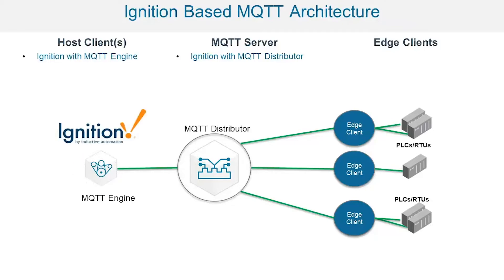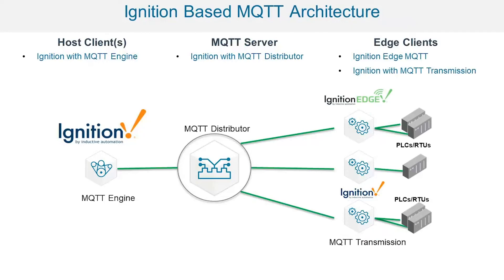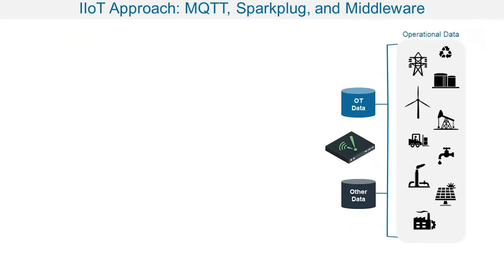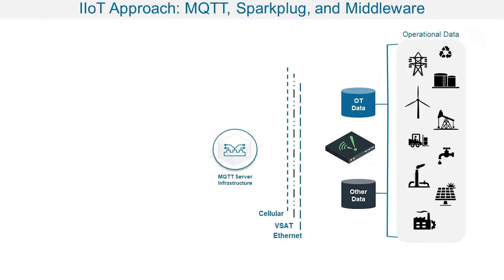On the Ignition Gateway, we install MQTT Engine — an MQTT component that is Sparkplug-aware and can subscribe to messages coming through the MQTT server. On the edge, we have Transmission, which takes OPC UA tags and converts those to Sparkplug messages from the edge of the network. We take our devices in the field, interface to them locally using high-speed polling, and get information — not only what we were polling previously, but other stranded data. We then get an MQTT server infrastructure and establish our IP connections into a DMZ.